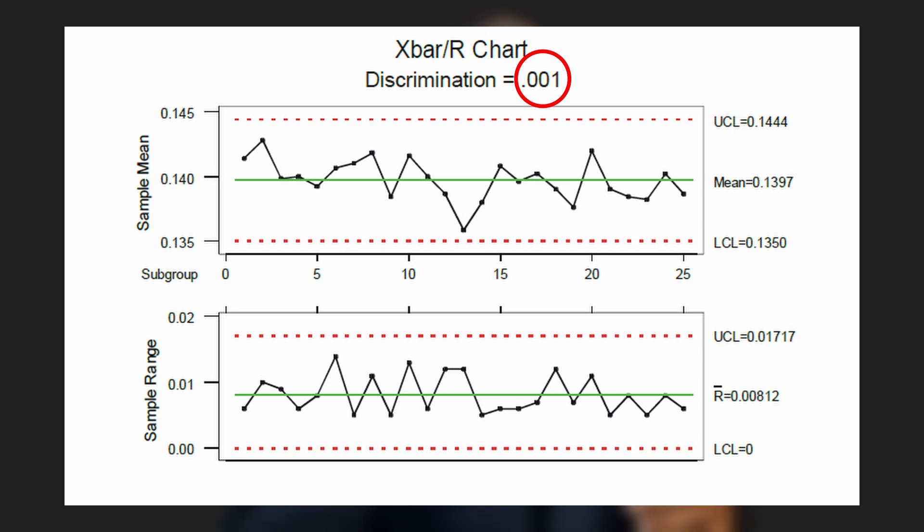The reason all points are now within control is simple — the instrument now has the capability to detect that error. If an instrument cannot find the variation which is in the process, it can result in either a Type 1 or Type 2 error: a good part may be rejected, or a rejected part may be considered good.